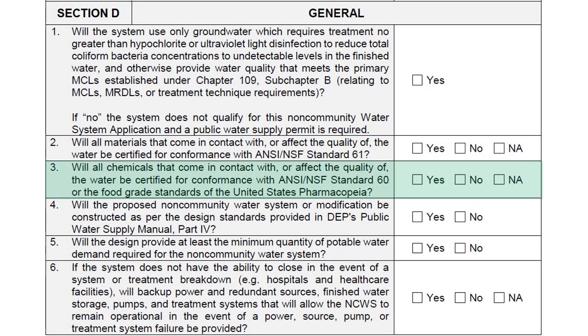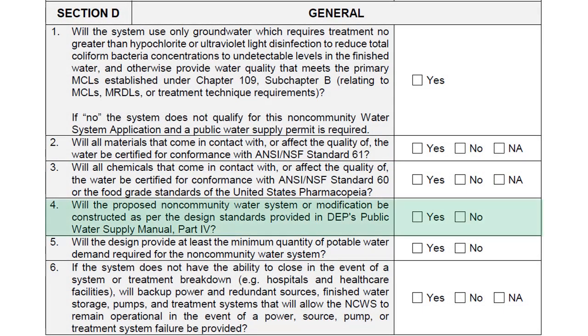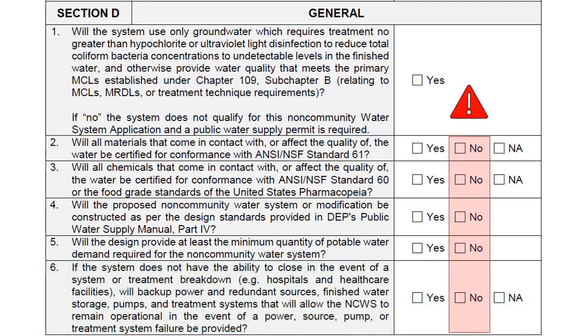All chemicals must also be acceptable by the department. If chemicals are certified for conformance with ANSI NSF Standard 60, they meet this requirement. If not, the department will review the specifications provided to see if the chemicals are acceptable. The system shall be constructed and/or modified as per the design standards found in the Public Water Supply Manual Part 4. The system design must provide at least the minimum quantity of peak daily water demand, with a minimum flow rate of 2 gallons per minute at each outlet or plumbing fixture. If the system does not have the ability to shut down, the water system must have a way to ensure continuous operation and supply of potable water. It is important to note that if any questions are answered no, the applicant must provide a detailed explanation of how the alternative design will meet the design requirements.